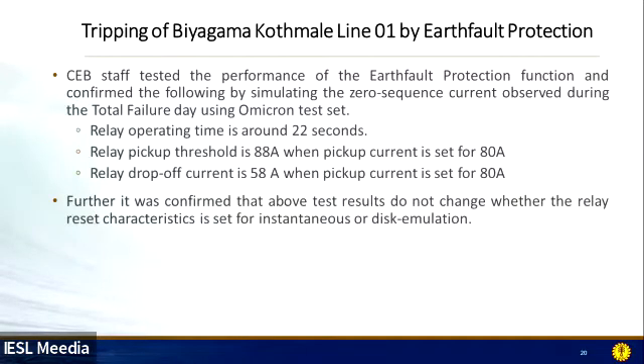Further, it was confirmed that the test results do not change whether the relay reset characteristic is set for instantaneous reset or time-delayed reset characteristics. In the manual it says different things, but when we inject the current and test the relays, the relay behavior does not change whichever reset characteristic you set. The relay behaves the same way.